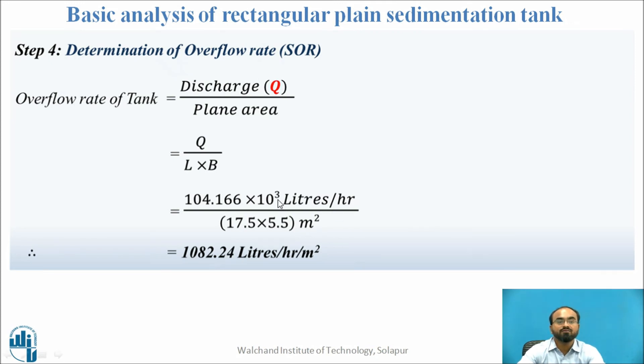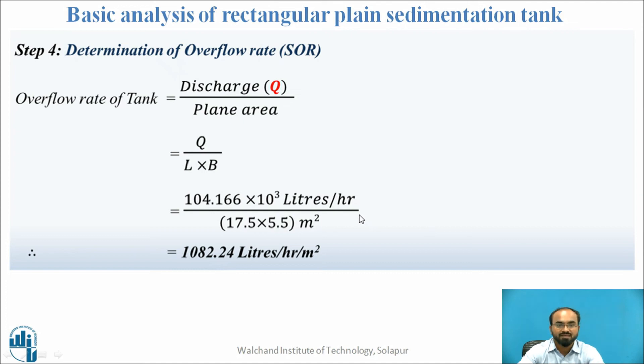For the overflow rate, the formula is Q divided by surface area (L × B). In liters per hour: SOR = (104.166 × 10³) / (17.5 × 5.5) = 1082.24 liters per hour per m². If the answer is needed in m³ per hour per m², use 104.166 directly without multiplying by 10³.